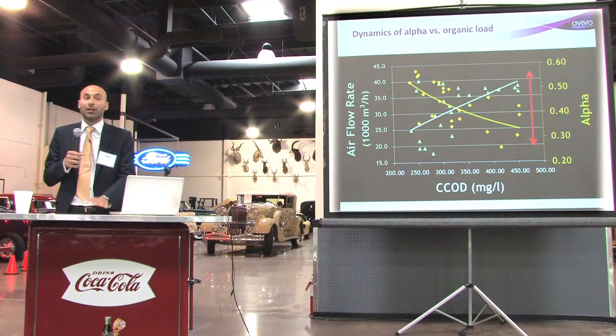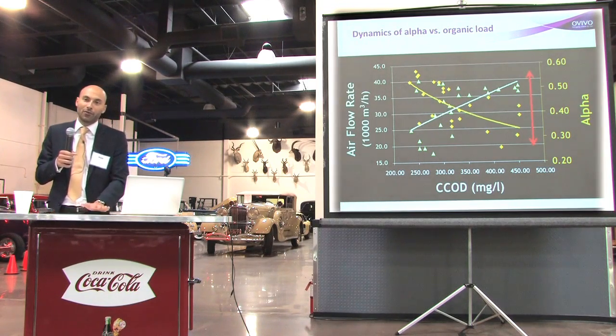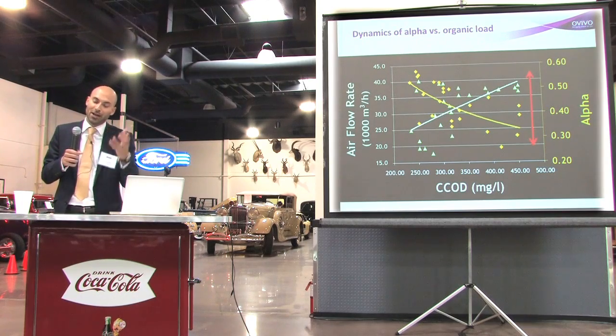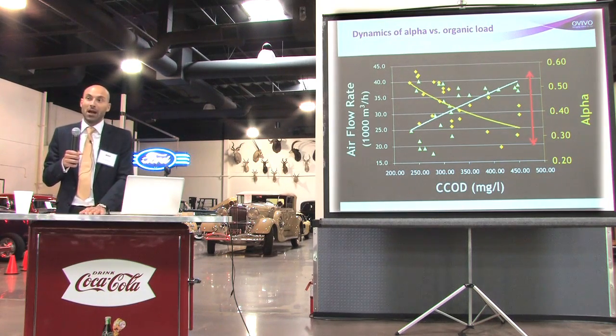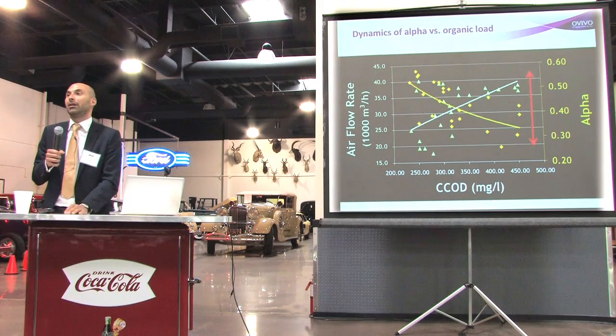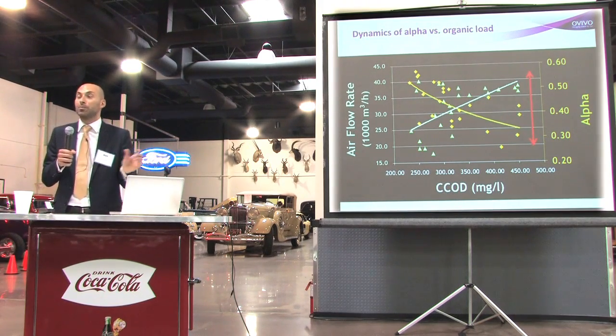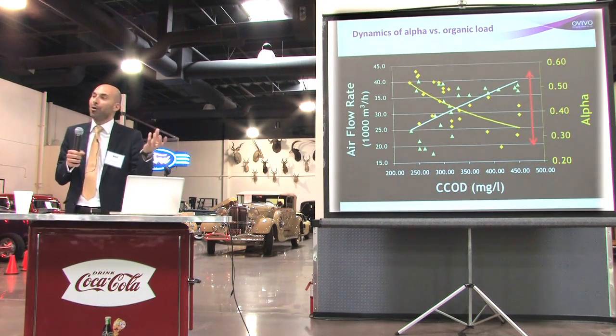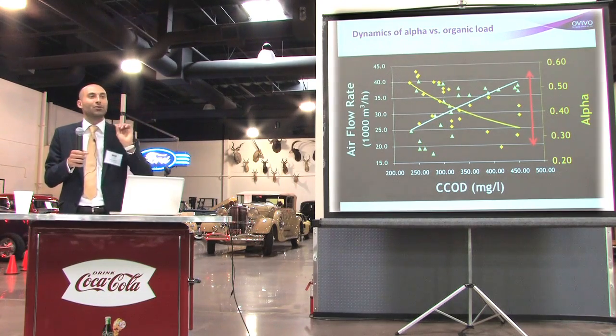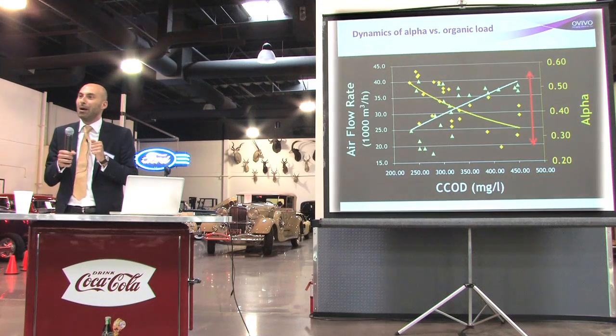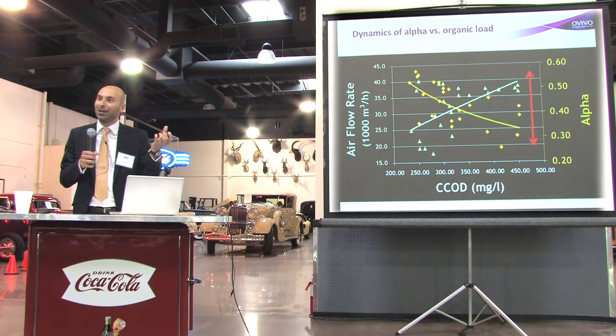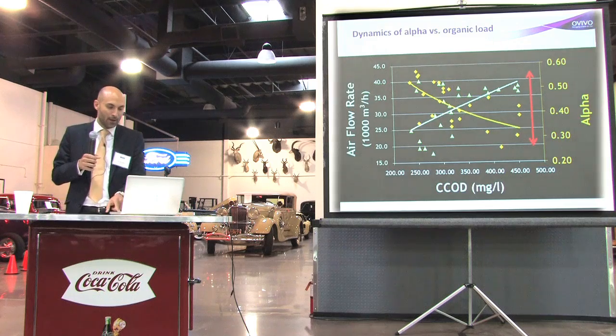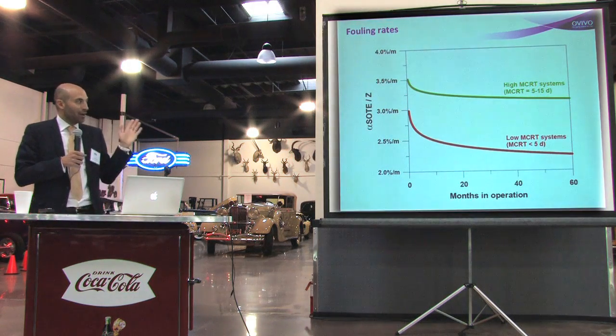Most of the carbonaceous matter that harms gas transfer is soap — from handwashing, showering, dishwashers, washing machines. Surfactants are everywhere, and while they're not the majority of COD, a fraction migrates very quickly to bubbles because surfactants are both polar and non-polar. They love to stick to the air-water interface — hydrophobic tail into the bubble, polar head into the water — and once they stick, they're chemically stable and form foam.